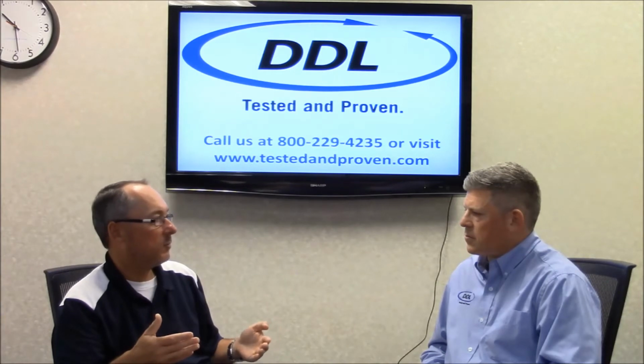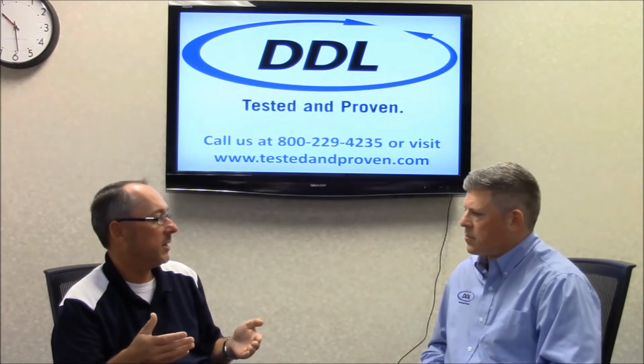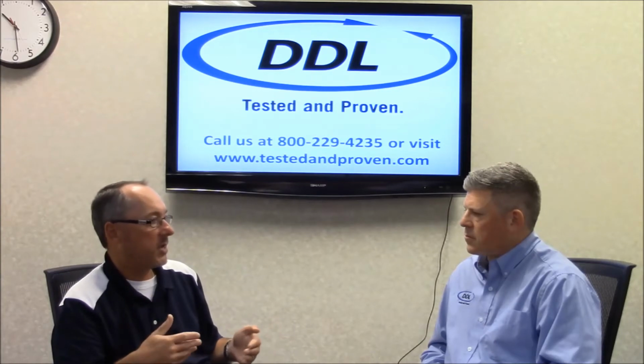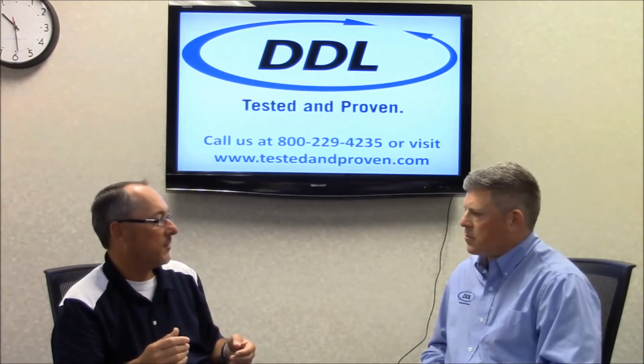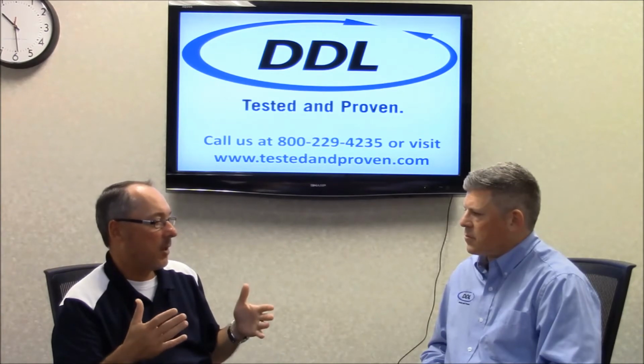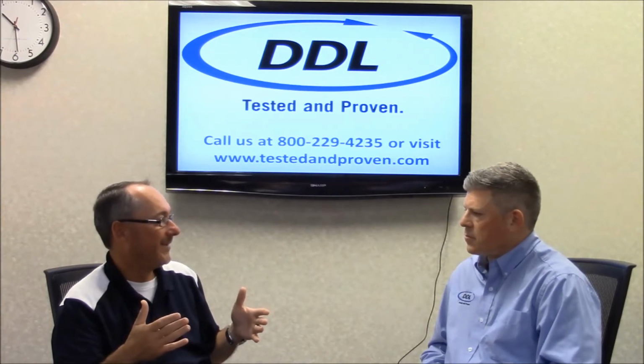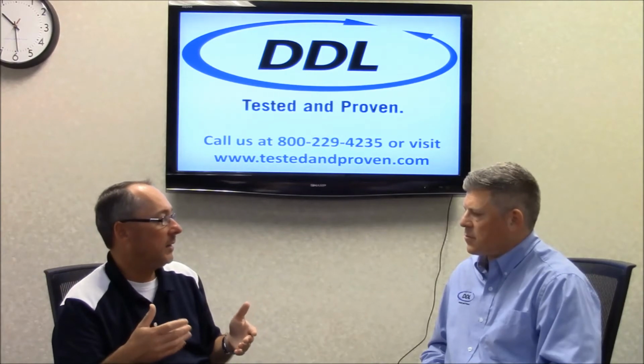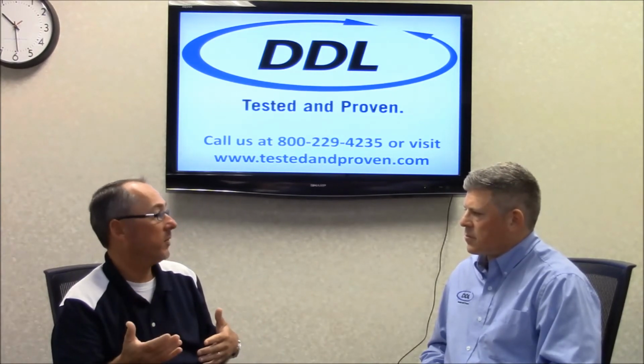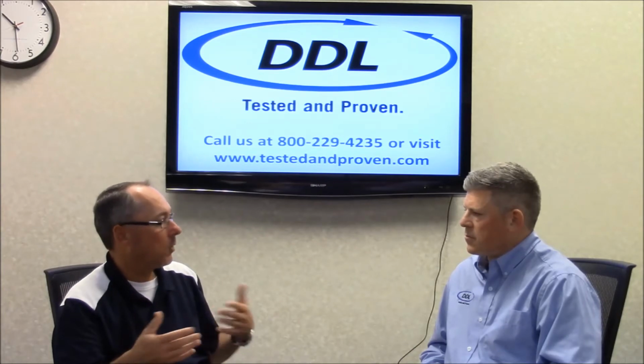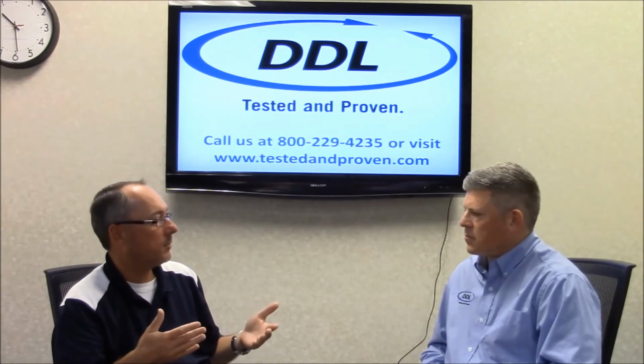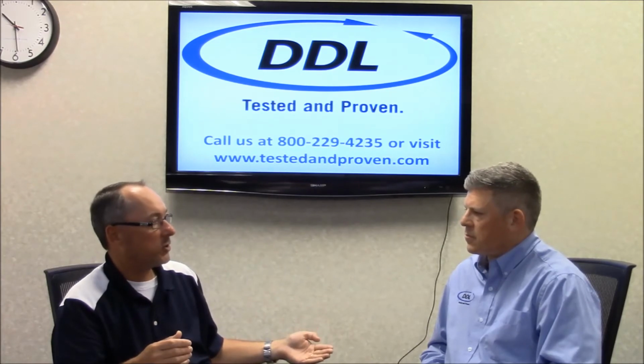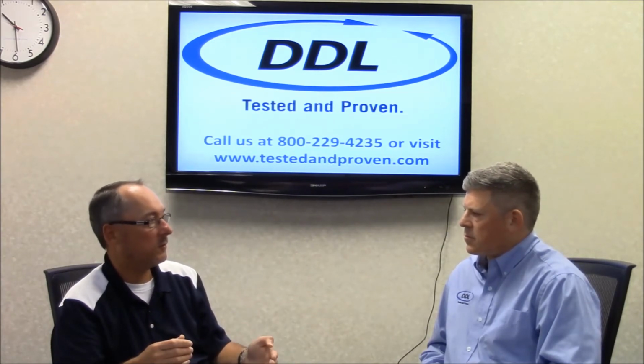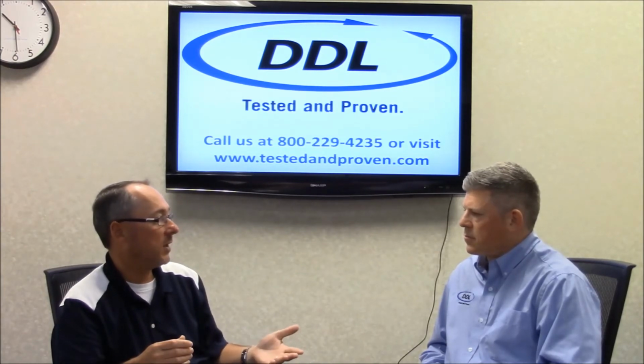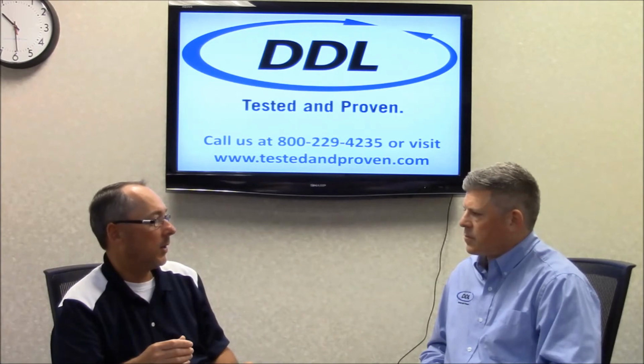So planning is probably the biggest number one issue I see immediately. If I have somebody call and say, you know what, I want to run something at 70°C, the first question out of my mouth is, you need this quickly. And typically that answer is yes, we need this data very fast. Well, what are you doing with that data? And if it's for a submission, then we'll go back through all of the aspects I've talked about earlier about how you get questioned on using this high of a test temperature when the standard counsels you not to go over 60 or take risk in going over 60. You got to have a pretty good justification. So that's probably the biggest pitfall I run into.